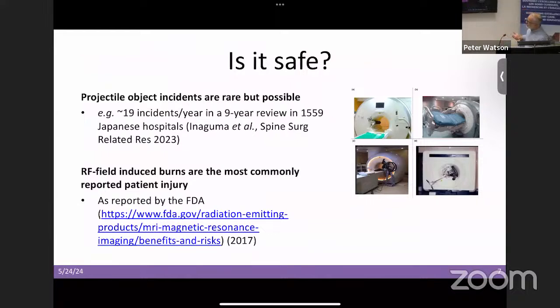The other important patient injury-causing factor is RF field-induced burns. In fact, they are some of the most commonly reported patient injuries as reported by the FDA. Now, the data from the FDA are a little old, but nonetheless, burns are a high source of patient injury. I spared you the photos of projectile incidents, all these large objects being pulled into the MRI scanner. If they all seem like old photos and old scanners, it's because they have happened a few times over time, but I have some more recent examples. I also spared you the picture of the RF-induced burns. They are pretty gory looking, and they can go all the way down to fourth degree if the wrong kind of device is involved in the examination.